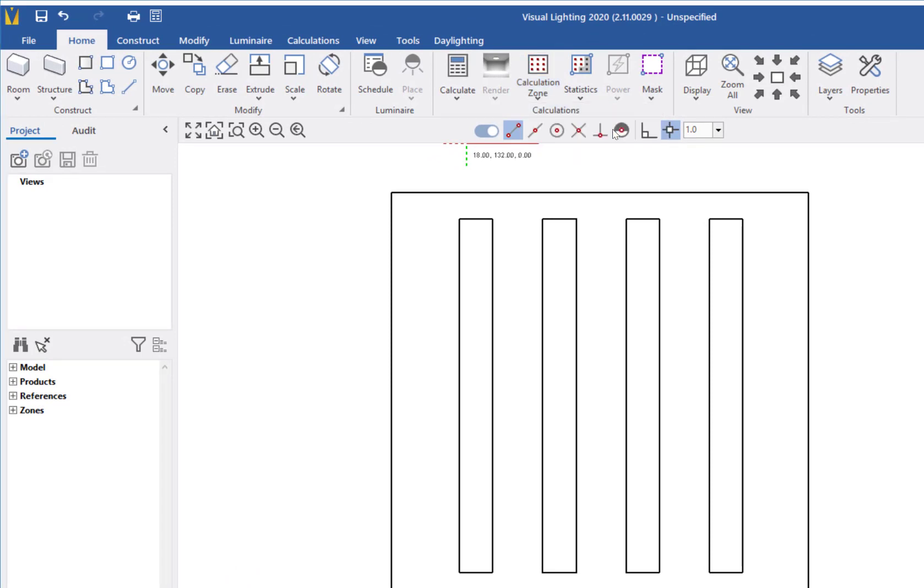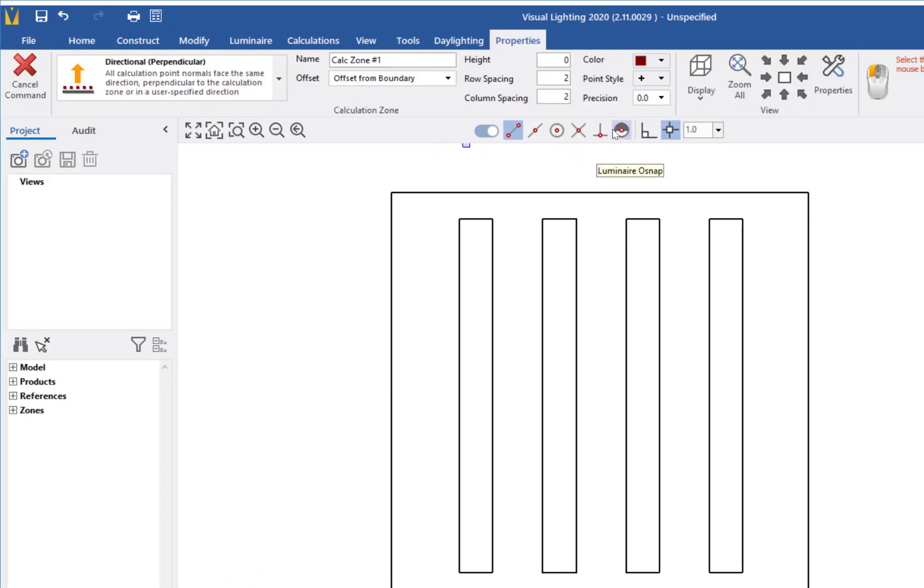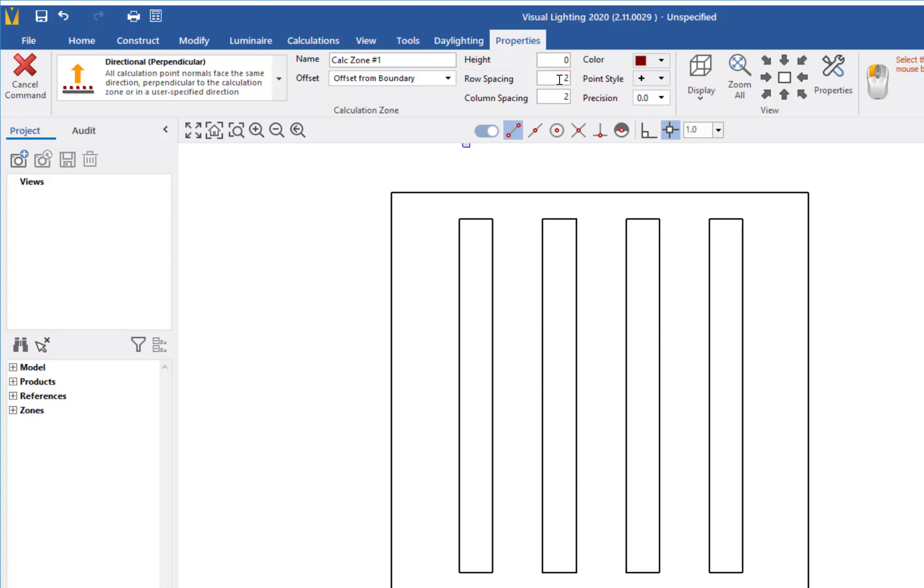In the Dynamic Properties, I can adjust the properties of the calculation zone, including the height from which the light will be measured. I will use the default height of 0 feet and then adjust the row and column spacing to 5 feet and name it Warehouse A.